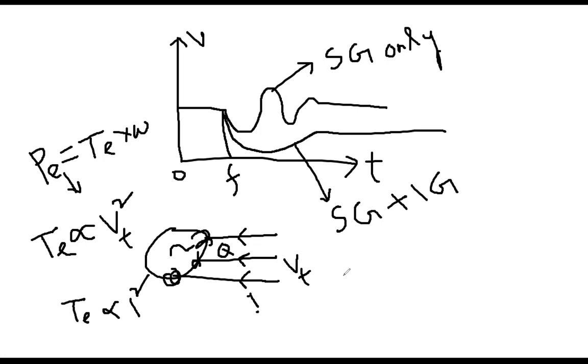We are not discussing that point. We are assuming before connecting any controller or protection means, what will be the situation, what is the stability condition - that's what we're discussing. So during fault condition, they will start drawing much more reactive power to compensate that electromagnetic torque, drawing more current and reactive power.